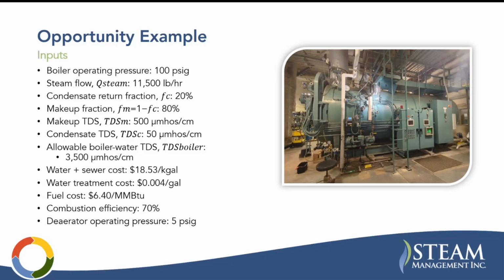And good water treatment is good. You can also reduce your blowdown by improving your blowdown control. So upgrading blowdown control. And sometimes these units will be packaged together with an improved blowdown control, and that helps smooth out the blowdown flow to the unit and promotes better heat capture.